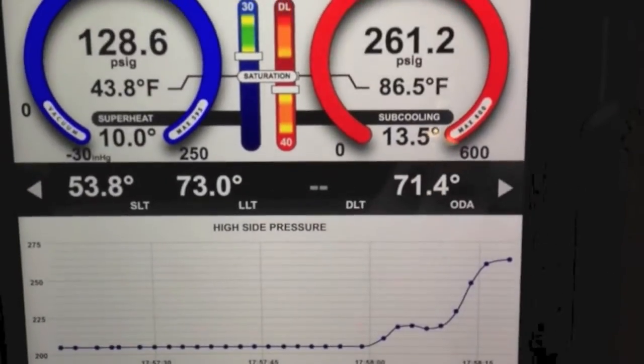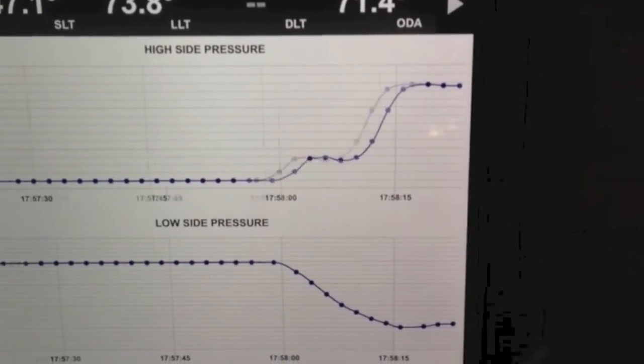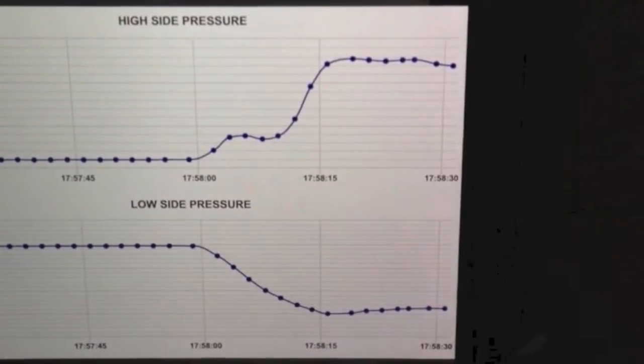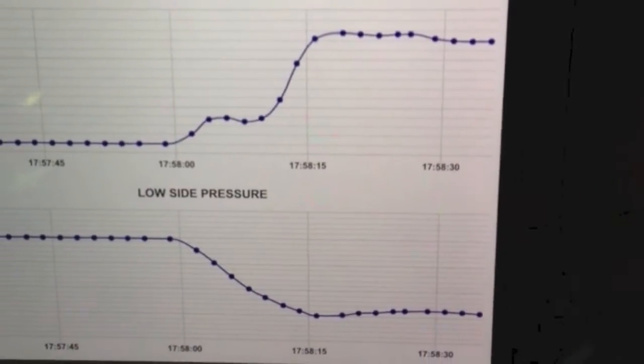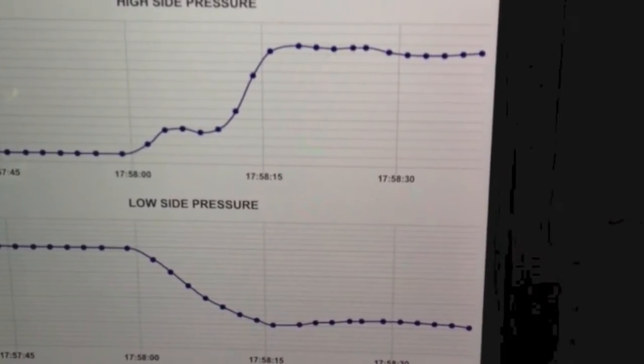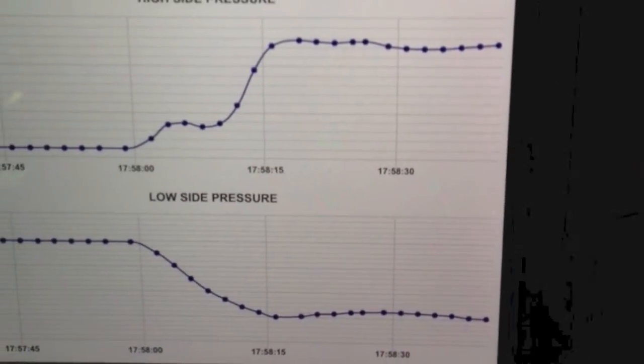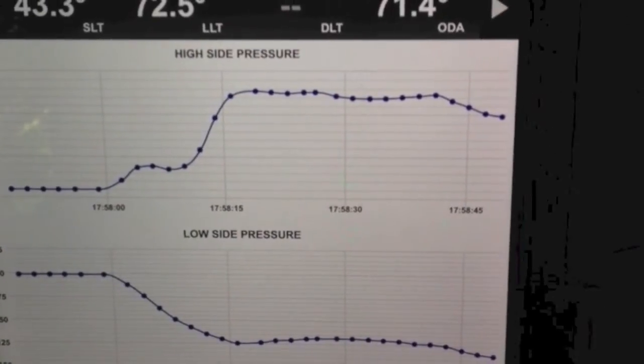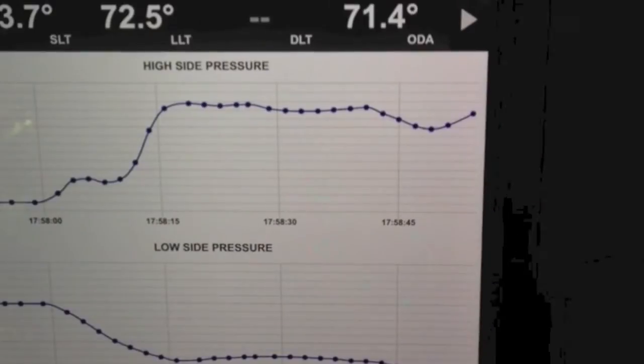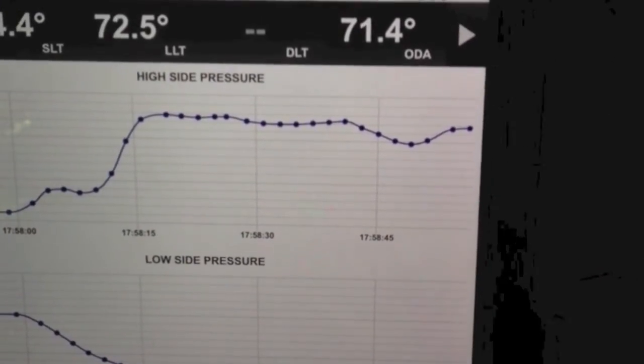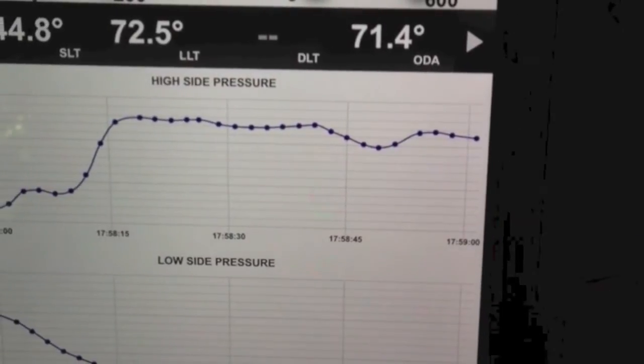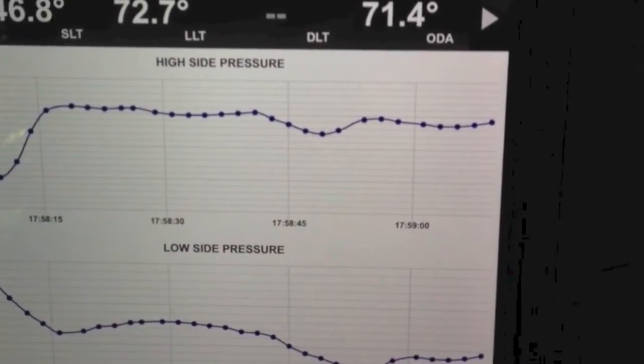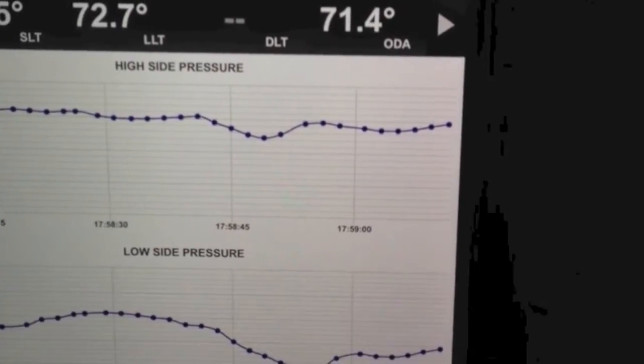So now the system's started up. We've got our gauges going — we're coming down on the low side and up on the high side. We'll let things stabilize. This particular graph I have set up to show 30 points of data. After that 30 points is gone, we're going to start wiping those points off the screen — that's what a trend is. It's set to trend every two seconds and 30 points, and the trends will auto-rescale to fit the display a little bit better.